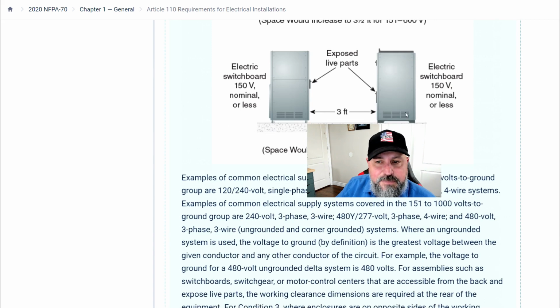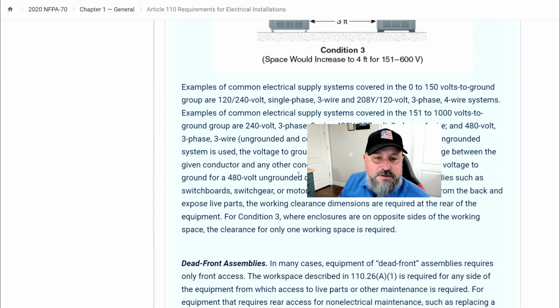Okay, got that? That's if it's 150, but space would increase to 4 feet for 151 to 600. Examples of common electrical supply systems covered in the 0 to 150 volts to ground group are 120/240 volt, single phase, 3-wire, and 208/120, 3-phase, 4-wire systems. Examples of common electrical supply systems covered in the 151 to 1000 volts to ground group are 240 volt, 3-phase, 3-wire, 480/277, 3-phase, 4-wire, and 480 volt, 3-phase, 3-wire, ungrounded, and corner grounded systems.